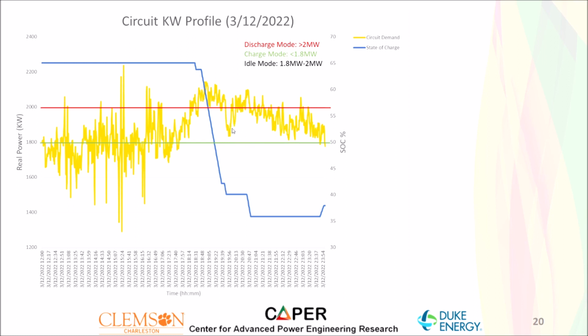But once we're in that 1.8 through 2 MW range again, it'll flatline, but once it sees that it's 10 minutes above that, it'll go back down. And then basically for the rest of the day, it's going to stay in that idle mode till midnight, where it just creeps under and it starts charging again.